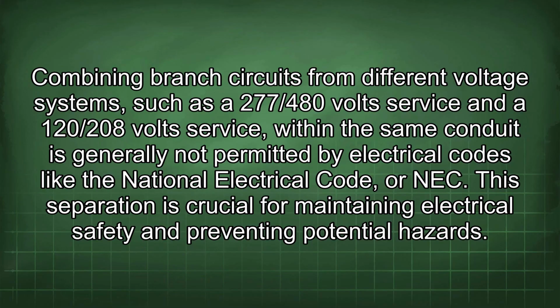Combining branch circuits from different voltage systems, such as a 277/480 volts service and a 120/208 volts service, within the same conduit is generally not permitted by electrical codes like the National Electrical Code, or NEC. This separation is crucial for maintaining electrical safety and preventing potential hazards.